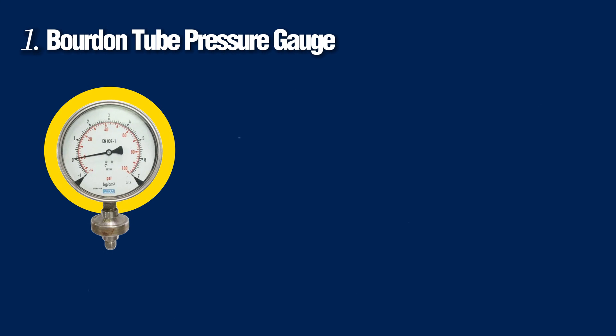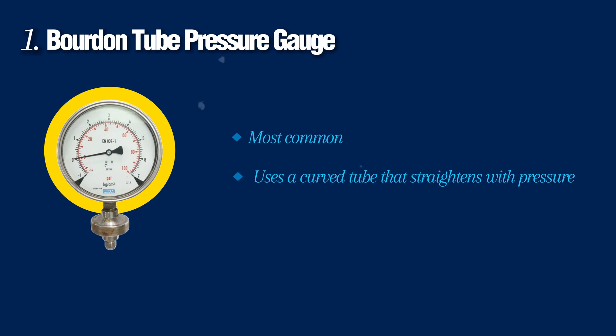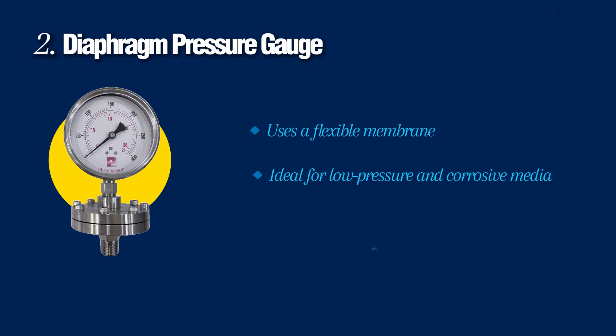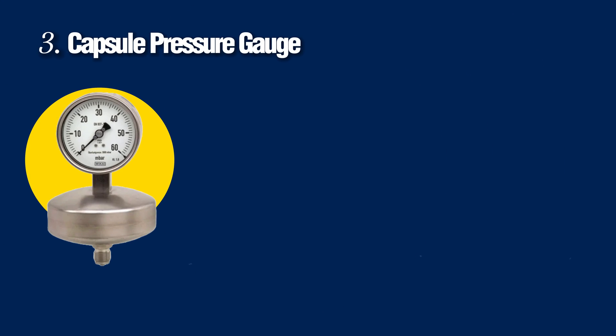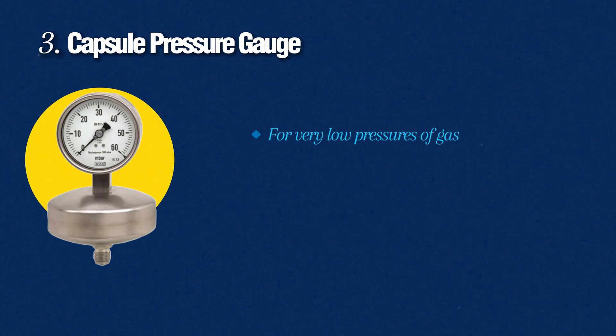Now let's cover some types of pressure gauges. The first one is the Bourdon tube pressure gauge — it is the most widely common type, uses a curved tube that straightens with pressure, and is used in water pumps, air compressors, and many more applications. The second one is the diaphragm pressure gauge, which uses a flexible membrane and is ideal for low pressure and corrosive media.